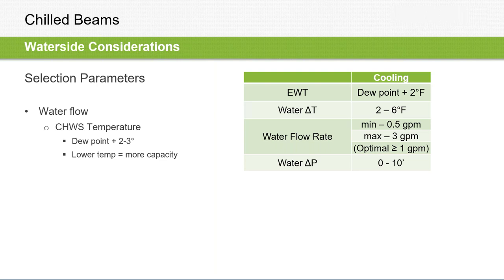We're actually limited there by the delta T across the water coil, and we found that this is what's optimizing. We're trying to reduce the CFM, so we're really optimizing for CFM and not really for delta T on the water side often. Then 0.2 to 0.5 GPM, all the way up to 2.5 or 3 is the maximum.